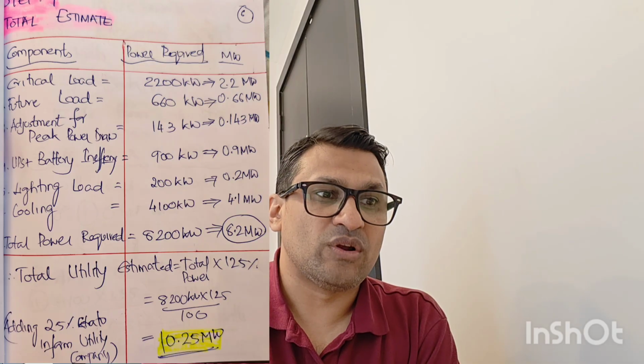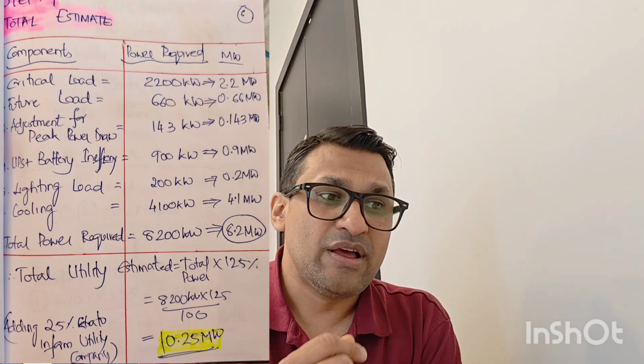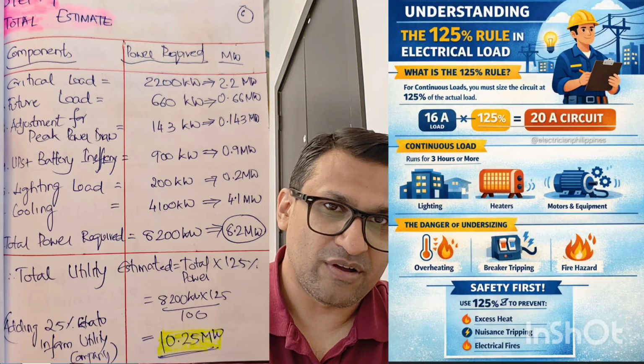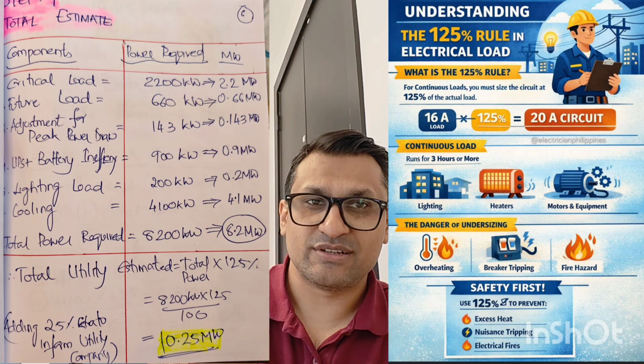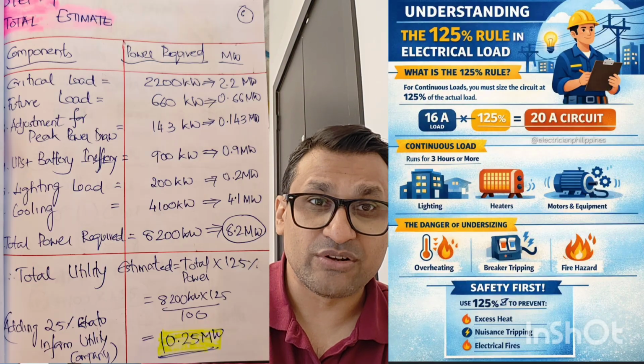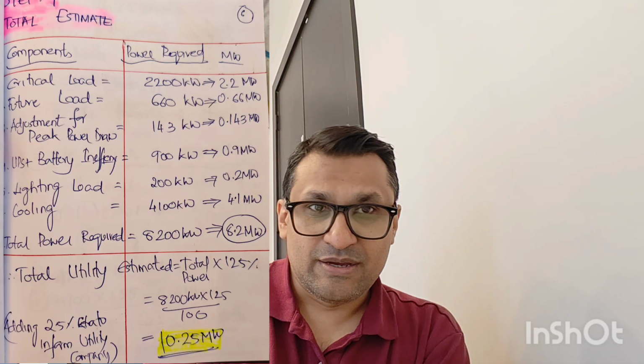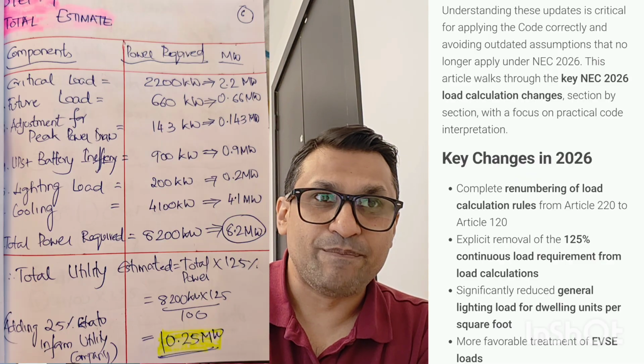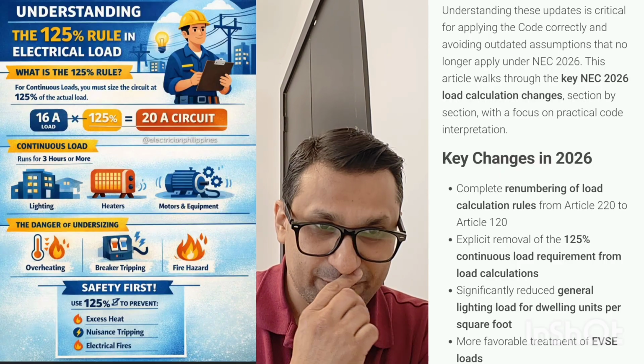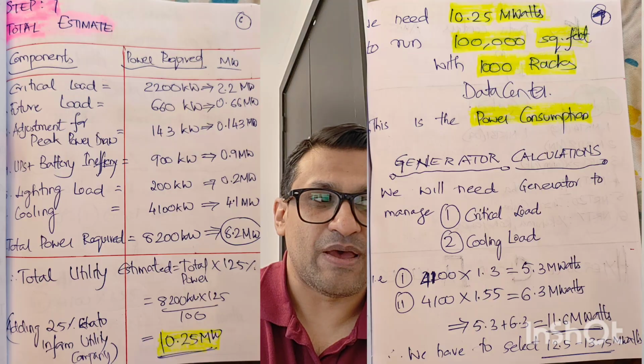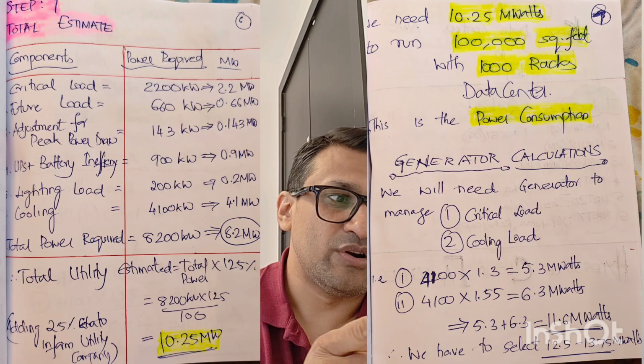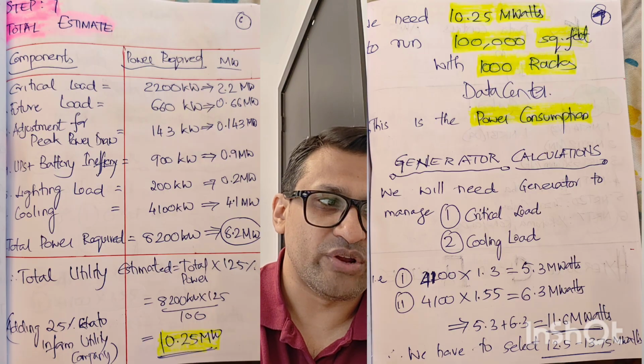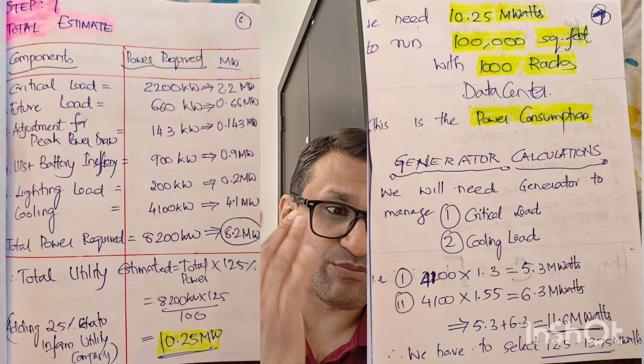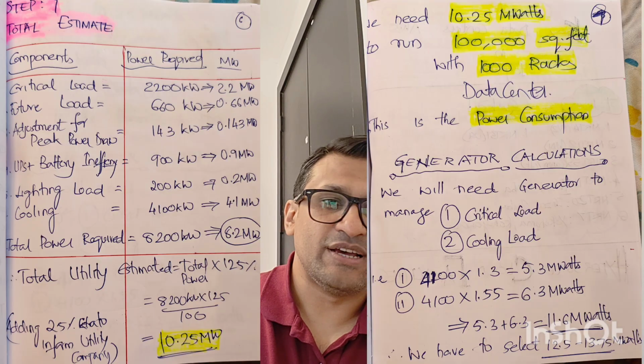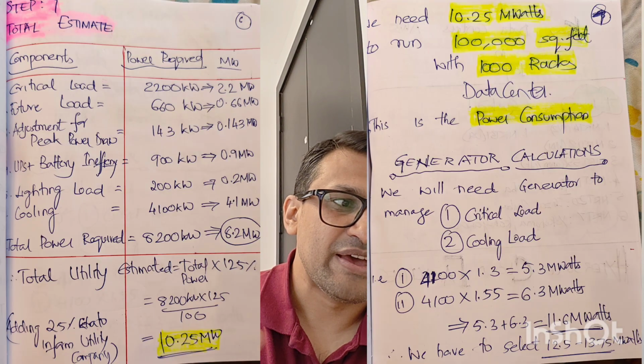Total utility estimate. Now, when you are requesting the power company or the utility company to provide power for a new data center, you need to give them a figure. They're going to ask you, what is the amount of power needed? We need to give them a near approximate estimate with the designs, considering the future loads and the future additions. You calculate the total power, which we just figured out, 8.2 megawatt times 125%. Adding 25% extra is important, because when you give it to your utility company, you always add 25% extra. So your total power times 1.25 is 10.25.